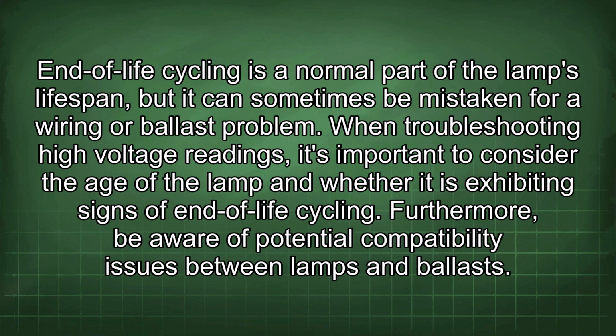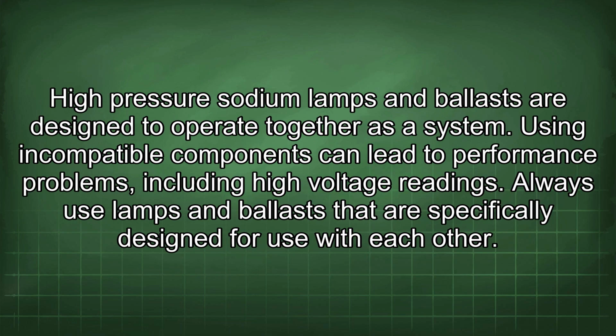Furthermore, be aware of potential compatibility issues between lamps and ballasts. High-pressure sodium lamps and ballasts are designed to operate together as a system.